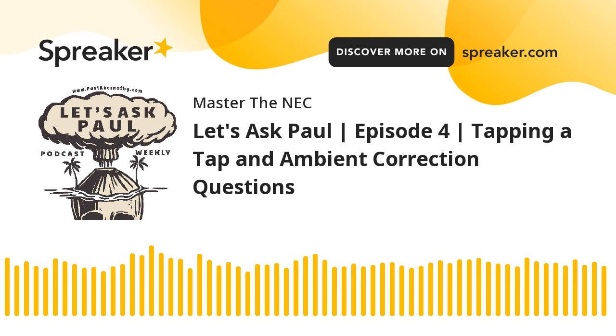I see this probably the number one thing that when it comes to feeder taps that I get asked around the country when I was doing the live seminars and live training and at different venues, there would always be a question. Somebody would raise their hand and go, yeah, but doesn't the feeder tap rules only apply to a conductor? No, it applies from the load side of the feeder overcurrent device.